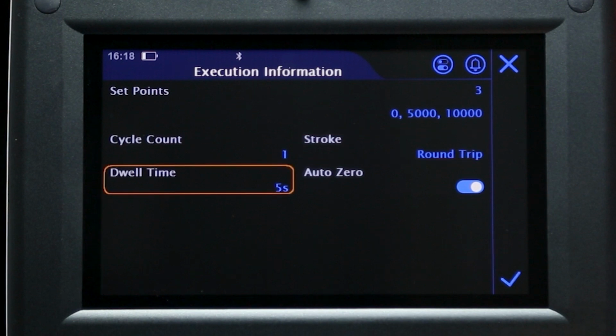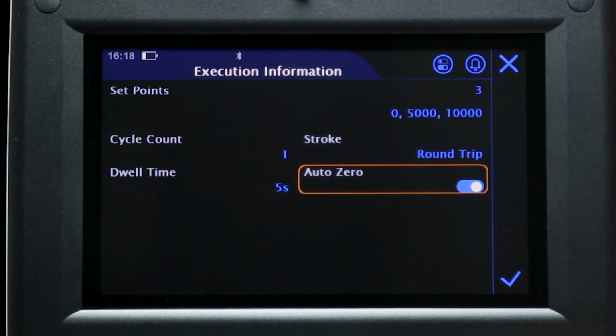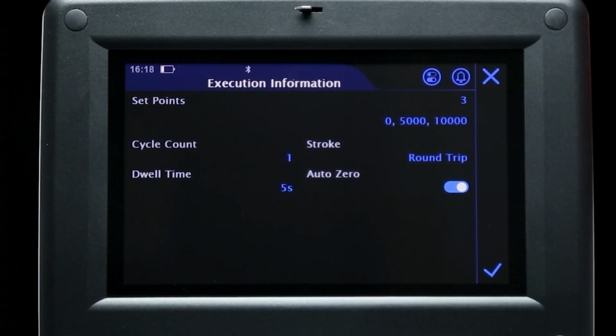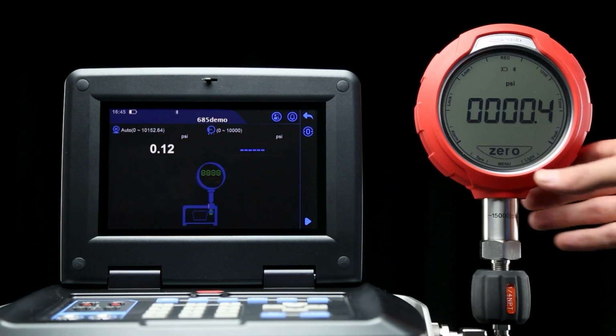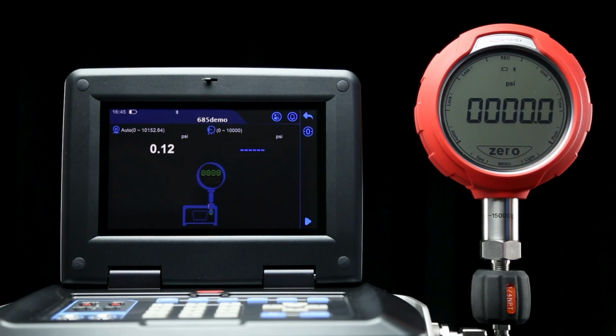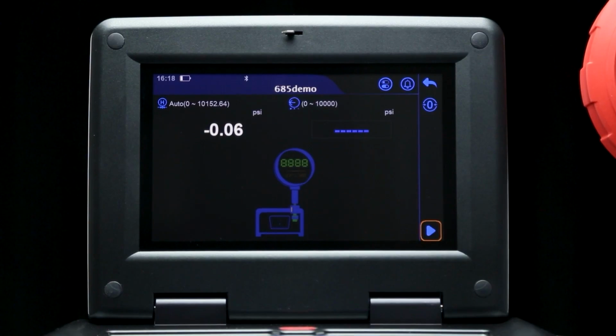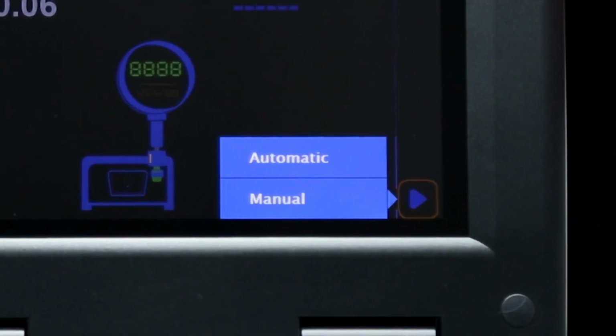Dwell time refers to the amount of time the 762 will wait to take a reading, and selecting the Auto Zero function will automatically zero the 762 pressure before the test. After the testing parameters have been set, press the checkmark button to move on to the testing screen. At this point, you should also zero your pressure gauge. Press the play button to begin the test, where you can select automatic or manual mode.